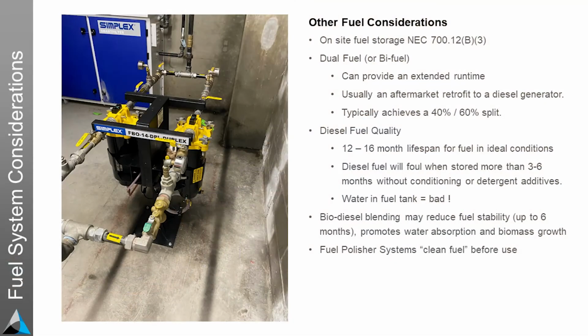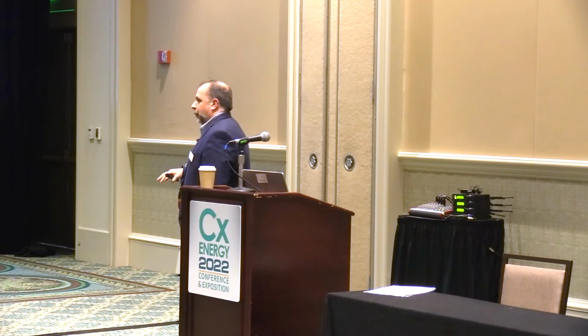Other considerations, other things I look for as I'm reviewing the system: are there different types of fuel, are the generators maybe dual fuel, or are they using biodiesel? Have they addressed the fuel quality issues? Because fuel can't just sit in a tank forever and expect the generator to run. Has that been addressed? Are there fuel polishers or fuel cleaners of some sort in the distribution system?